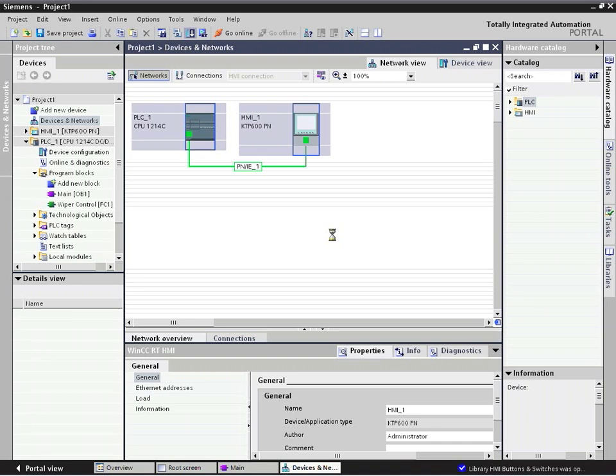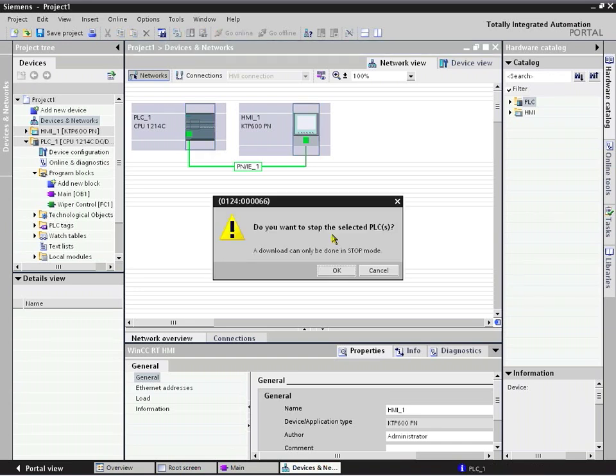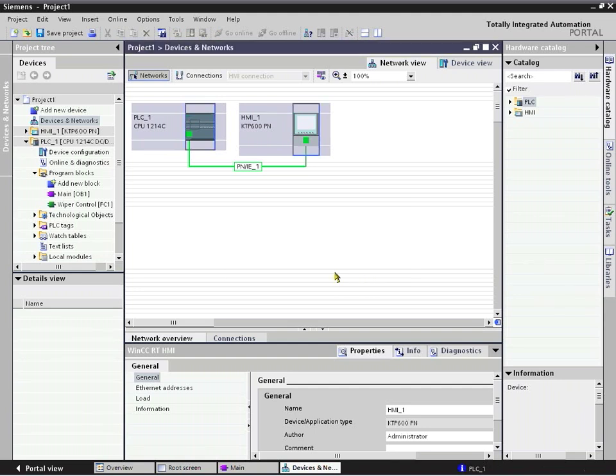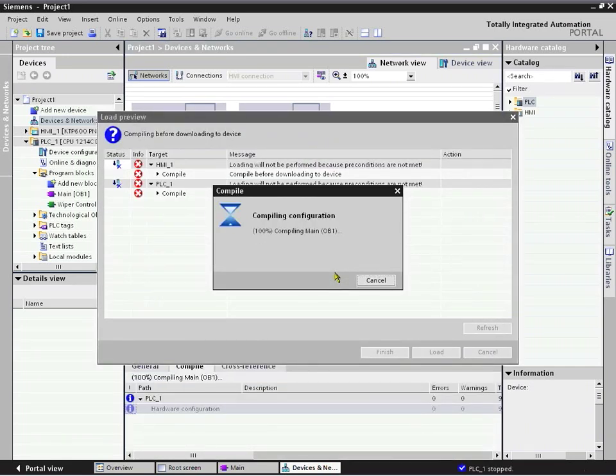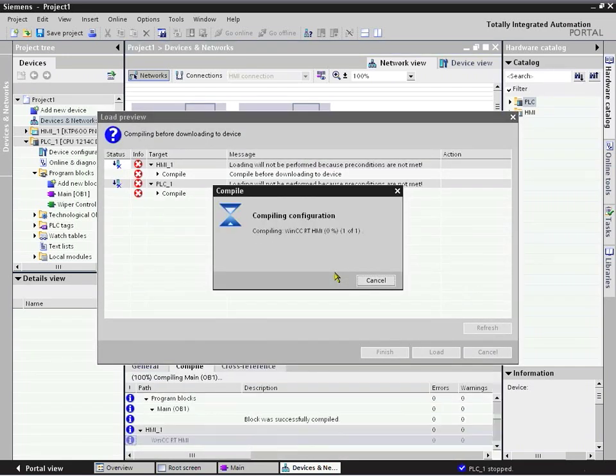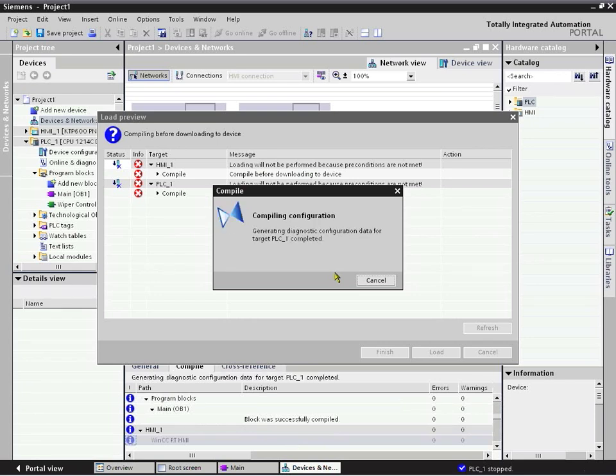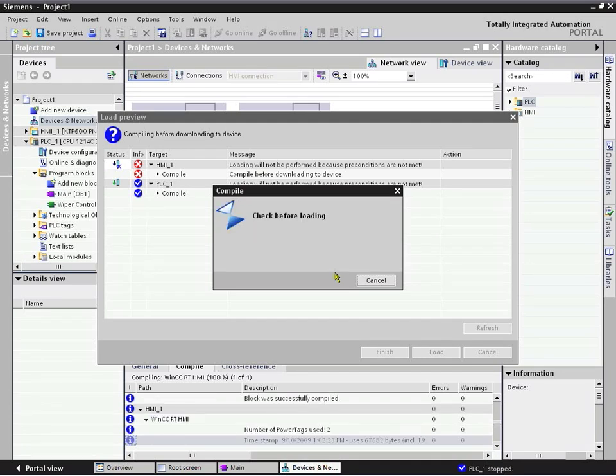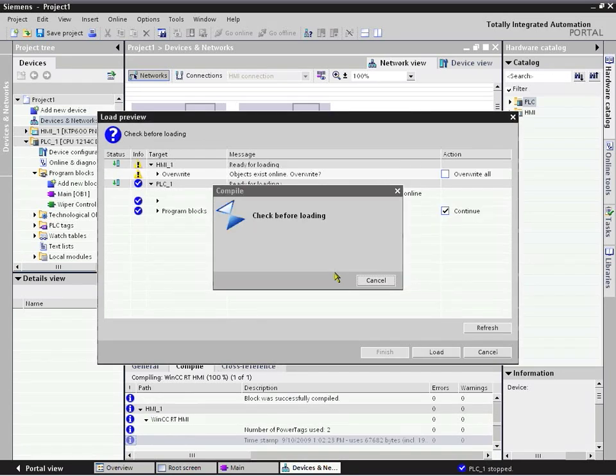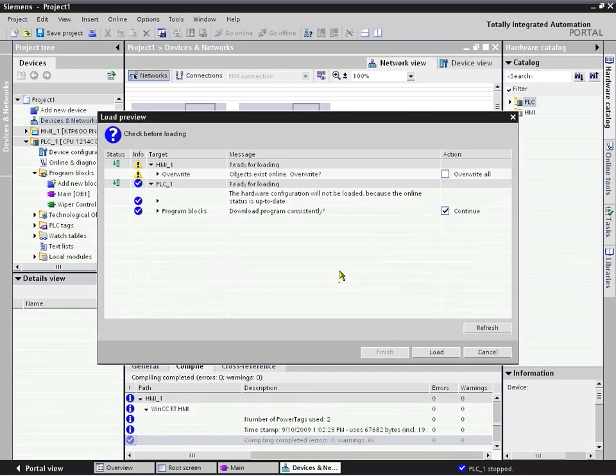It does automatic compilation, any kind of other rationalization, detects that the PLC is in stop mode, asks you if you want to put it into start mode, and complete the download and compile on all the configurations. Since this connection is on Ethernet via the programming PG or laptop and through the network that it is on, you can download all these simultaneously without having to do any other communication configuration or move cables around or anything that's quite time-consuming in updating a system that has both HMI and controller.